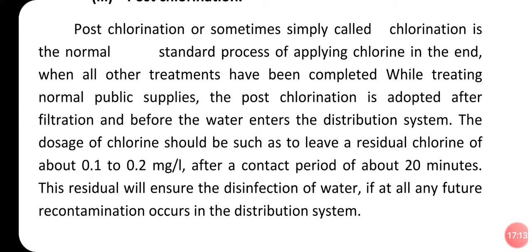distribution system. The dosage of the chlorine should be such that it leaves a residual chlorine of about 0.1 to 0.2 milligram per liter. But in any case, the residual chlorine must not exceed 0.2 milligram per liter. That is the case after a contact period of about 20 minutes. Generally, chlorine will be supplied to the water and it is left for 20 minutes for full spread in the water. And after that, if the residual chlorine is checked, it must not be more than 0.2 milligram per liter. So this residual chlorine is very important.